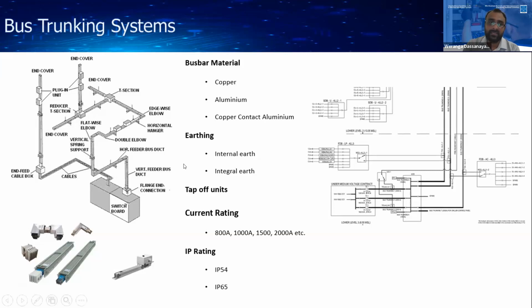Then in this kind of busway system there are two types. One is internal earth and the other one is integral earth. That means some busways are available with 5 conductors: inside the busway there are 5 conductors for 3 phases, neutral and earth. Some busways use their housing as the earth, so inside the busway there are only 4 conductors, for 3 phases and neutral. The housing is used as the earth. That is called integral earth. So when you go to the site, you can see these 2 kinds of busway systems, and you have to identify whether it is an internal earth or integral earth.